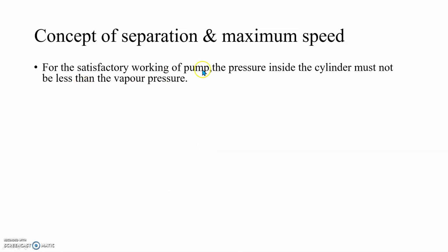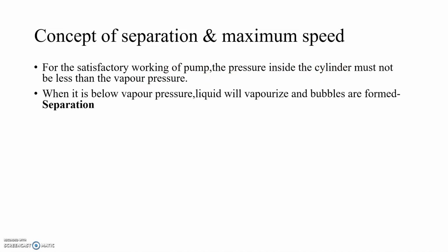For the satisfactory working of the pump, the pressure inside the cylinder must not be less than vapor pressure. When it is below vapor pressure, liquid will vaporize and bubbles are formed. We call this phenomenon separation. The separation phenomenon is similar to the cavitation phenomenon, which we already studied in the previous modules, associated with centrifugal pump and with reaction turbine.